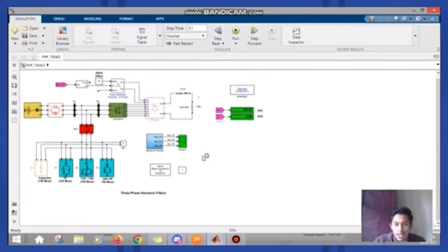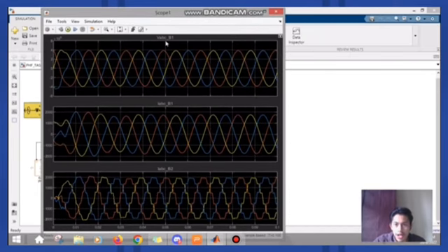After we click the scope, it shows the output waveform of the voltage for B1, current for B1, and current for B2. For the voltage B1, it shows a perfect sinusoidal waveform. The highest peak of the waveform is 0.4 megavolt. Next, for the current for B1, the first two waveforms show ripple here, but after that it becomes a perfect sinusoidal waveform. The highest peak for the first two waveforms is 2 kiloampere, and the rest of the waveform has 1.8 kiloampere.